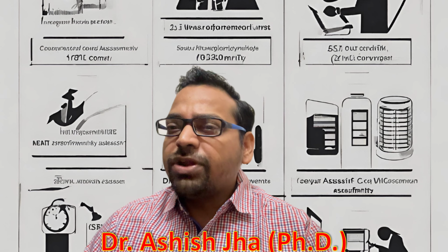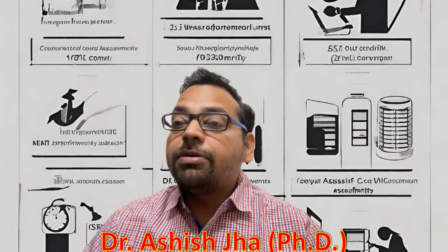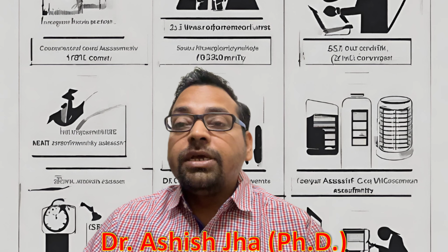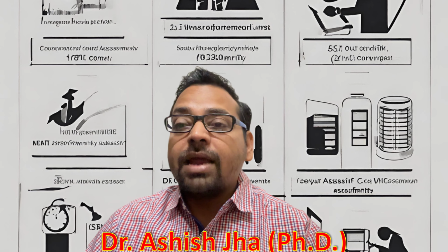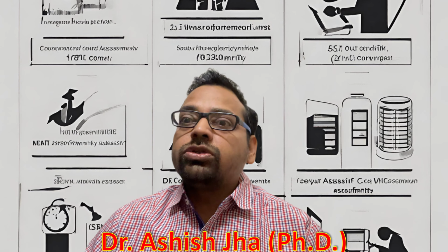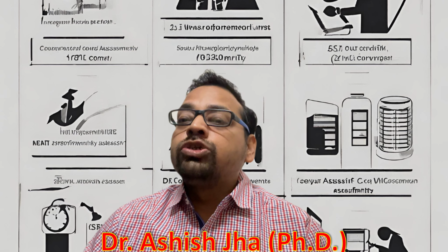After assessing and evaluating each and every piece of medical device related information submitted by the manufacturer, if the regulatory or authorizing body feels that everything is correct and as per standards, rules and regulations, only then they authorize or certify CE marking and other things, which help the manufacturer to place their medical device into the market.